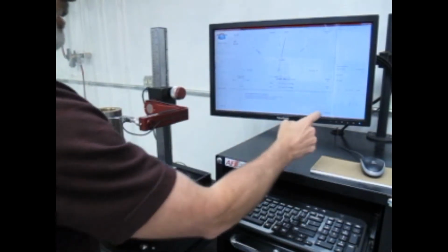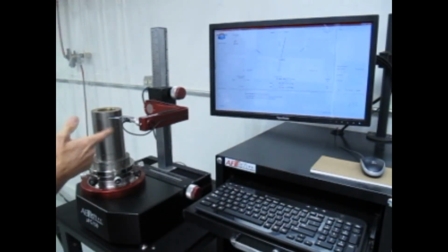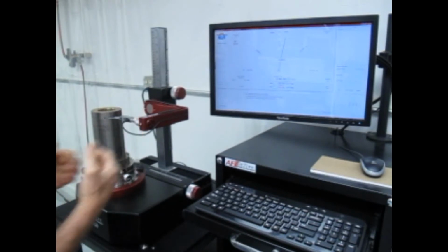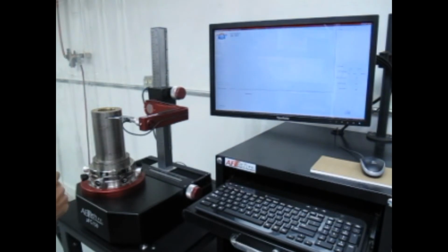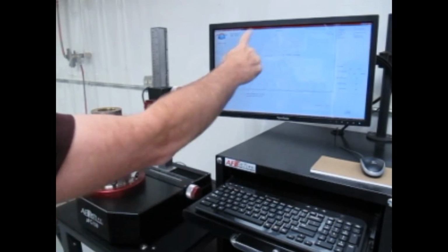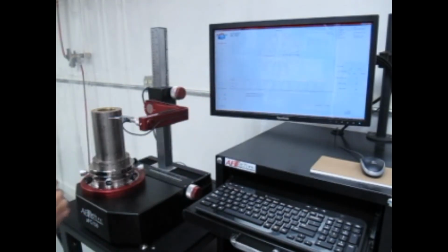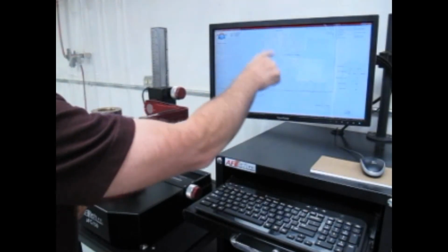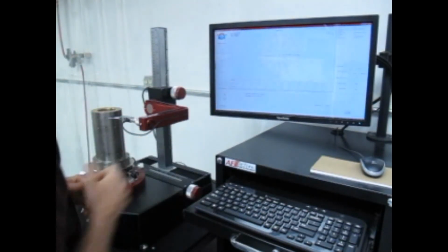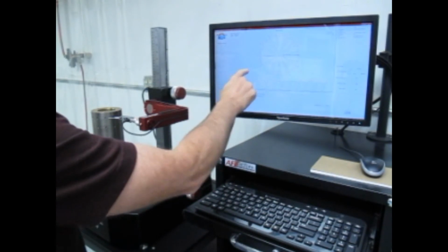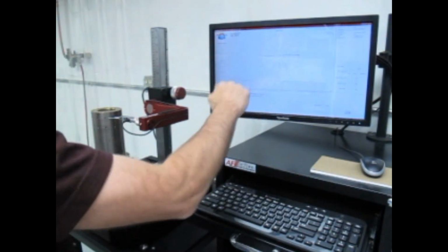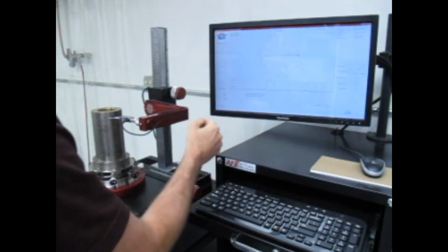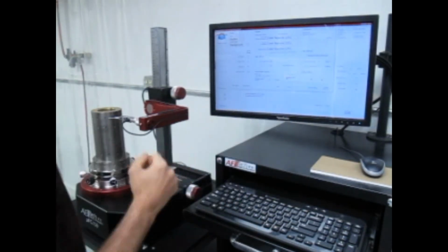So I'm going to take a roundness measurement using the motor, and each time it drops into those, the software is going to automatically take that out and give me the roundness of the rest of it. And it'll plot that without those exclusions in there. I've got a polar plot listed here as well as a strip chart, and you can see those dropouts and how it's trimmed the bottom of each of those. Now, you can see how it drops down into the hole, and then it starts to trim off, and as it comes back, I've got it only set right now to 1 degree before and after.